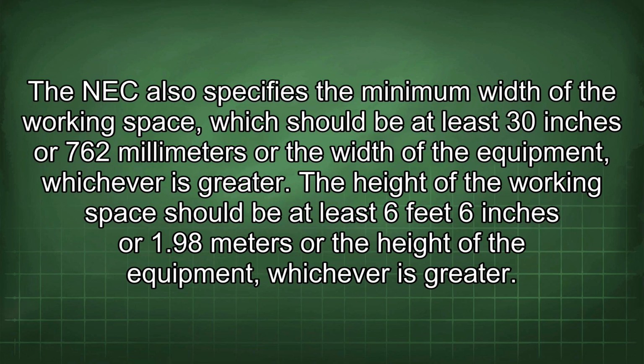The NEC also specifies the minimum width of the working space, which should be at least 30 inches or 762 millimeters, or the width of the equipment, whichever is greater. The height of the working space should be at least 6 feet 6 inches or 1.98 meters, or the height of the equipment, whichever is greater.